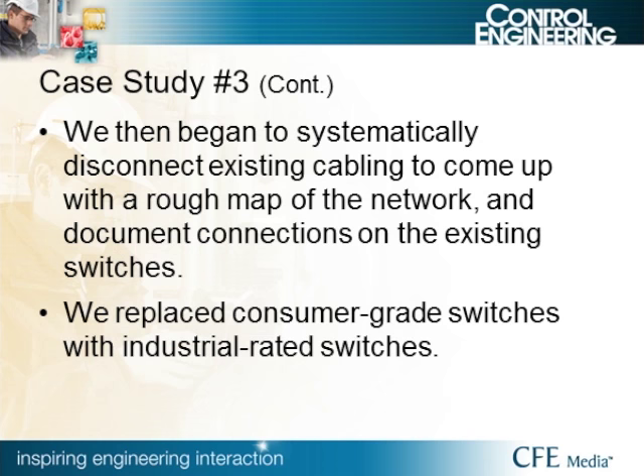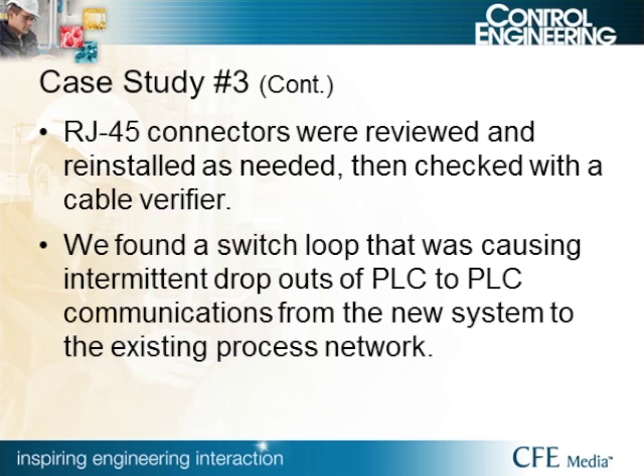Once the plant was down for installation, we traced out connections as much as possible and found switches buried up in panels — including an unmanaged switch hidden in a corner panel that nobody knew about. We also found cabling issues: bad connectors, individual conductors cut during sheath removal, and cables that had been pushed against something over the years, developing a crimp. We then systematically disconnected the existing cabling to map the network and document all connections. We replaced consumer-grade switches with industrial-rated switches. We also found switch loops causing intermittent PLC-to-PLC communication dropouts — because the original switches were unmanaged, spanning tree protocol was not enabled.